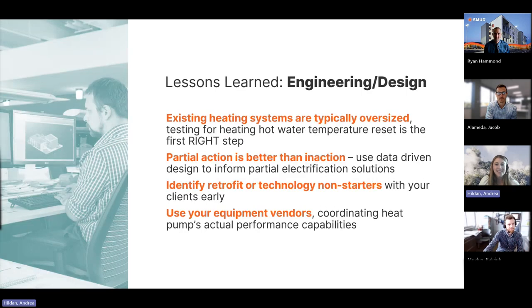Awesome. Thanks, Raleigh. And then Jacob on the engineering design side. Yeah, I love all the takeaways so far from this. From an engineering standpoint, the first one here is existing heating systems are typically oversized. And what I mean by that is, sometimes they installed a heating system a long time ago, they rounded up to the next traditional boiler size or standard boiler size. And since then, they've done envelope improvements. They've done a lot of things to the building to make it run more efficiently. And sometimes those systems are just very oversized.